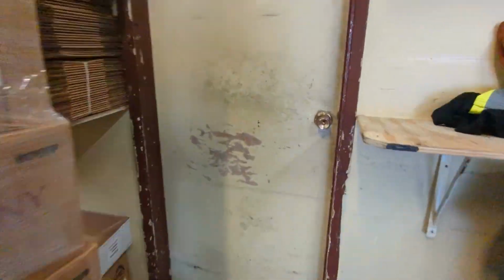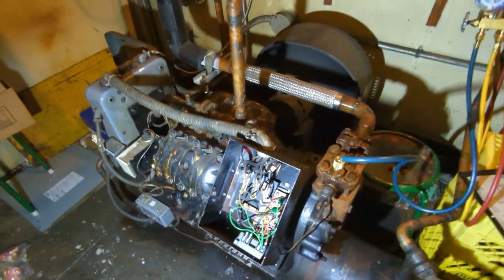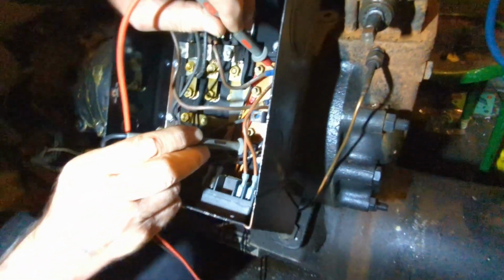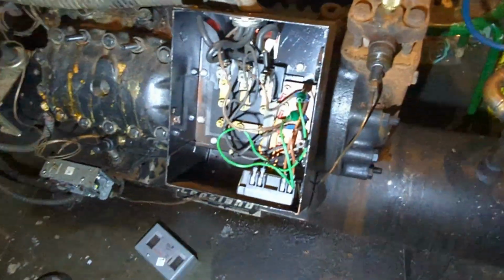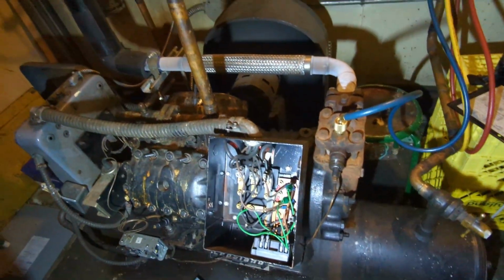We also had a call to our meat supplier's main walk-in freezer, the one where we replaced the big compressor back in March. They've got another smaller compressor in that same room, and it wasn't starting at all. We found the compressor protection module faulty, preventing the compressor from starting. So we grabbed another one, and they are so expensive - I just cannot believe how much controllers cost.